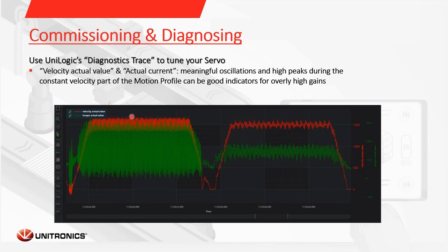Here you can see higher oscillations for current and velocity, and here everything is more controlled and better. If you were close to the machine with a system acting like that, you would probably hear squeaky noises or see vibrations — and with proper tuning, that won't happen.